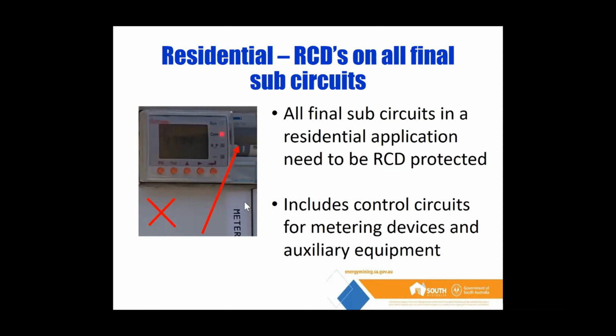So the circuit protecting this metering device isn't a consumer mains. It's not a sub-mains. It's a final sub-circuit. And 3000 says that all final sub-circuits in a residential application have to be RCD protected. So for the guys out there installing these types of things in switchboards, just because it's within the switchboard doesn't mean that it's exempt.